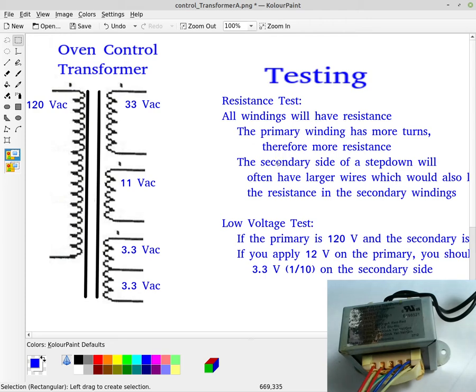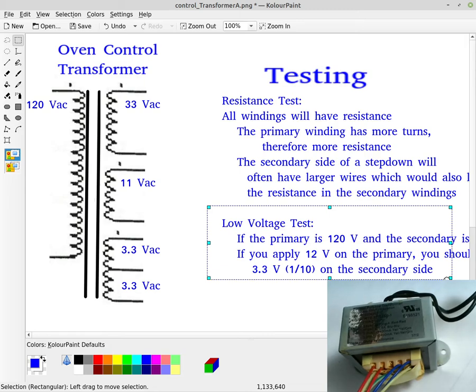Now, another way to test your transformer would be to actually apply a voltage to it and see whether you're getting that return voltage on the other side. So the first thing we'll do here is test for resistance and verify that there's definitely a problem with the bad transformer. And then I'm going to apply a voltage, but I'm going to be using a function generator here. So I'm not going to hook up 120 volts to this transformer to test it. What I'm going to do is only hook up 12 volts.